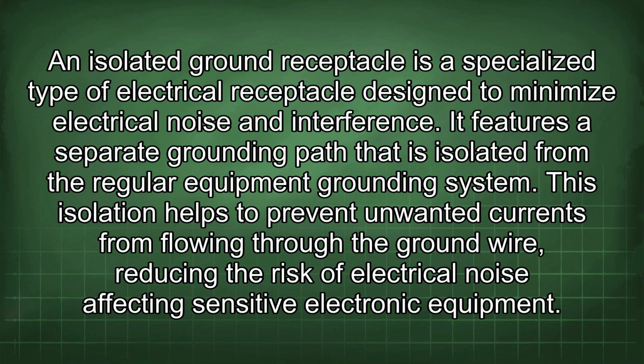An isolated ground receptacle is a specialized type of electrical receptacle designed to minimize electrical noise and interference. It features a separate grounding path that is isolated from the regular equipment grounding system.